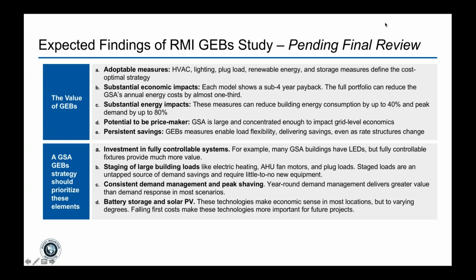For GSA, and I think the takeaway for other building owners as well, is that a GEB strategy should focus on fully controlling loads and control systems, and, as Monica laid out, the integration with the utility and the interactivity of different systems with one another, so you can stage large building loads so everything doesn't come on at once driving peak demand, but different equipment turns on at different times without significant impact on how the building is operated. It's just a little more intelligence as to when those loads come on.